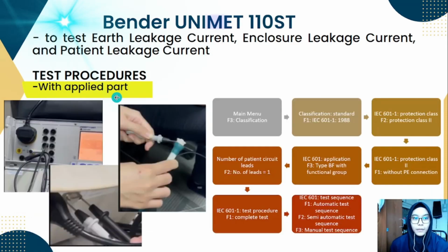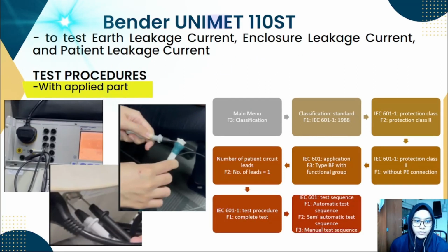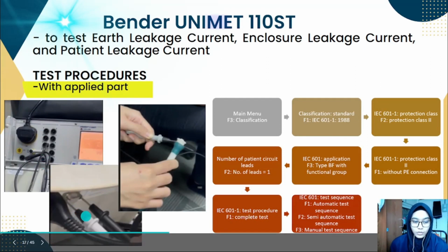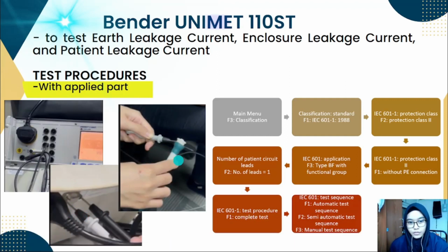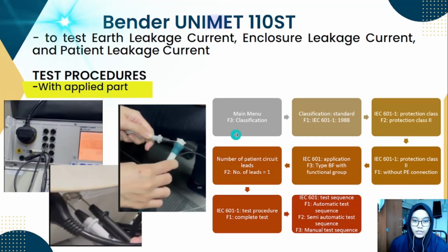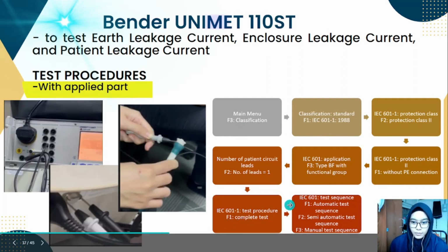Next, for the Bender with applied part, we can find the earth leakage current, enclosure leakage current, and the patient leakage current. For this one, it is the same, where the Bender safety analyzer connects to the tonometer, then the 3-pin plug of the tonometer connects to the Bender. Then we have the probe connected to the conductive part and the earth of the tonometer, and there's one more probe we connect to the applied part. Then, as before, the test can be conducted by choosing the following options on the monitor of the Bender. First, classification, then the same IEC 60601, protection class 2 without PE, type BF, and for the lead, we choose the one lead because we only have this one applied part. Then we choose complete test, then automatic test.